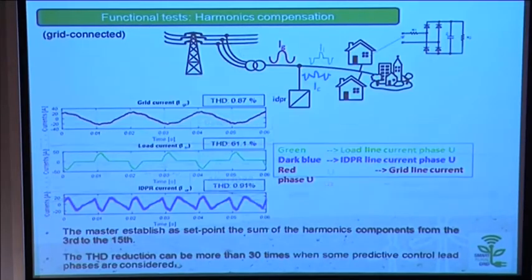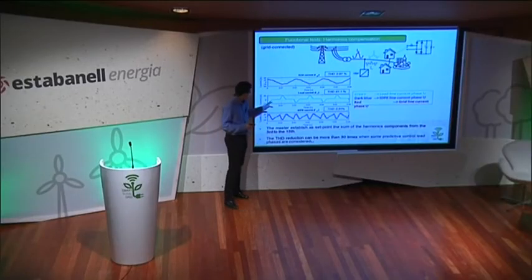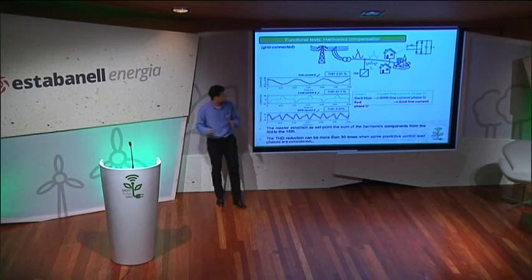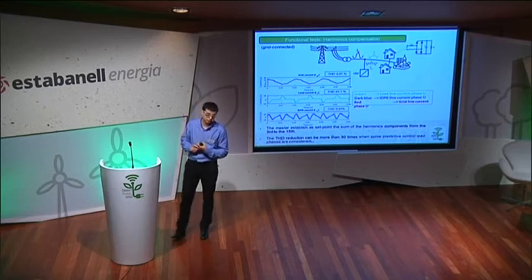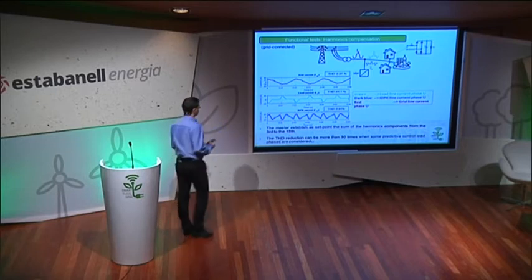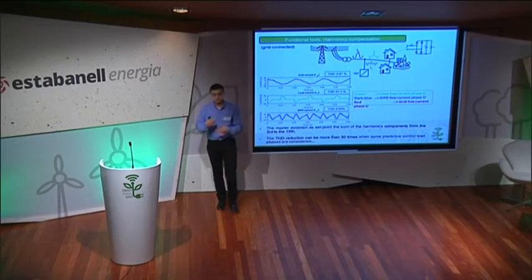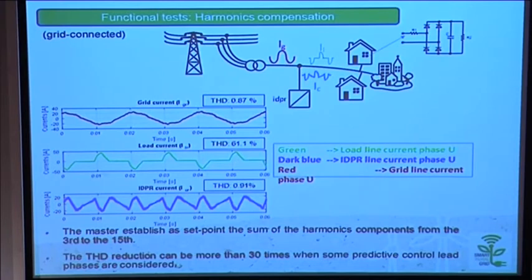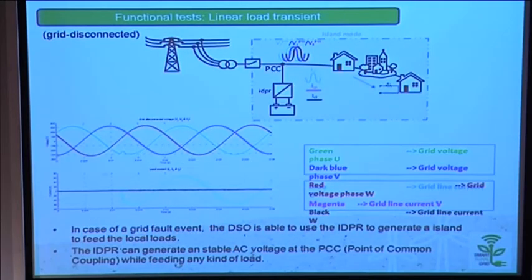Another example, also in grid-connected mode: we can have an aggregated load that, suppose, is a really nonlinear load. And this is an extreme situation. But for example, imagine that we have a load with this profile that represents about 61% of THD in terms of current. The IDPR is able to supply all the harmonic components except the 50 Hertz component, which is supplied directly by the grid. So the grid sees only less than 1% of distortion, and all the distorted components are supplied by the IDPR. This is all for the grid-connected mode, but what about the grid-disconnected mode?